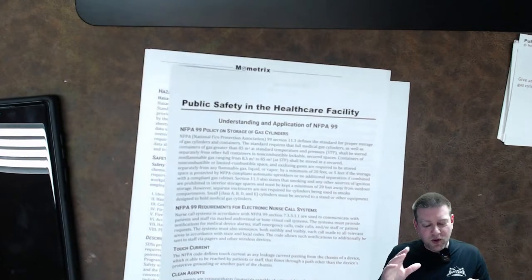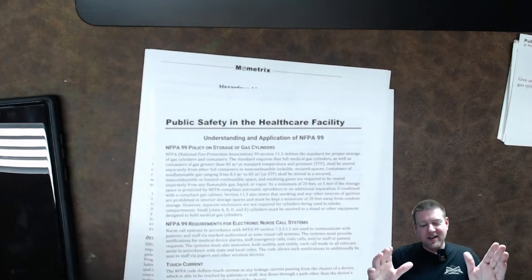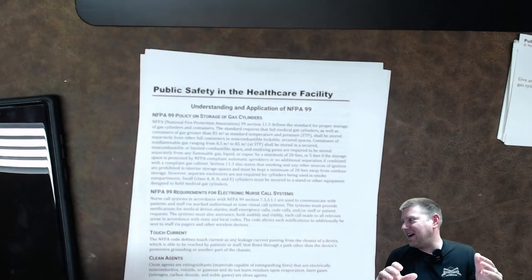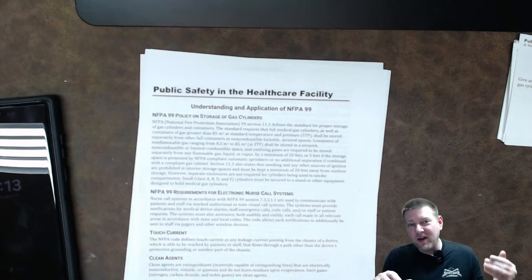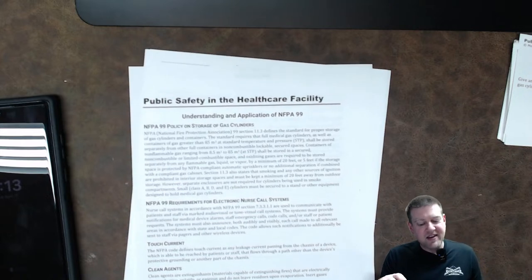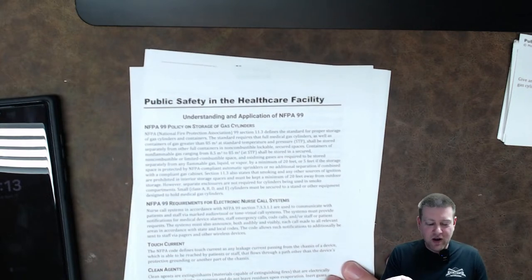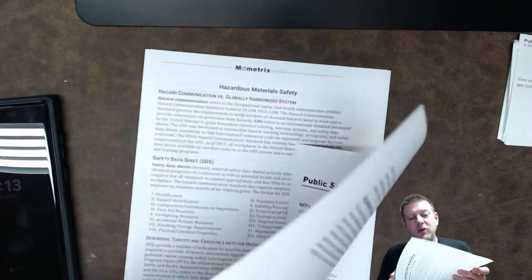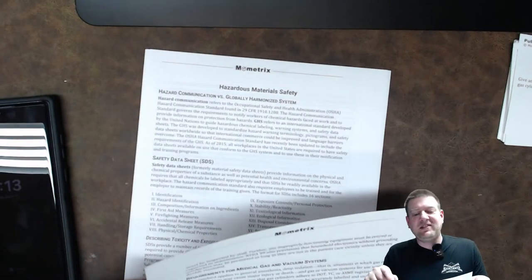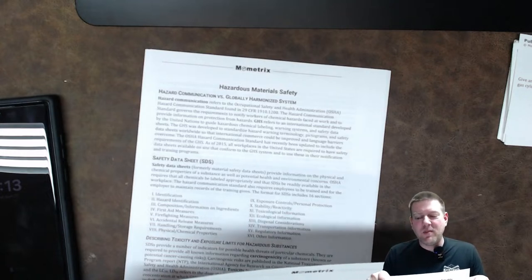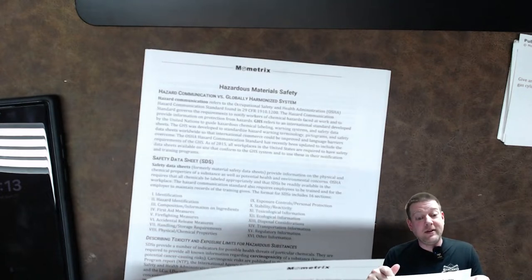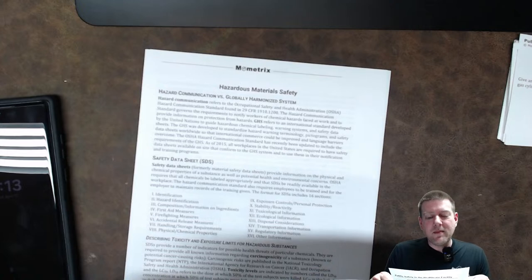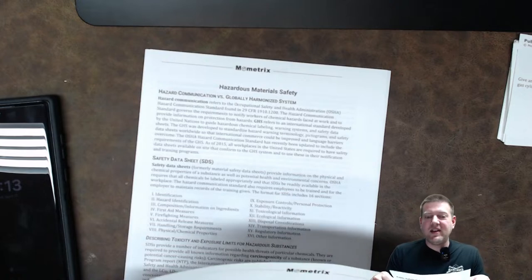Plug-connected, portable, non-medical electronics. Okay, guys, this is one where every hospital has a different policy. I get that. I understand that. However, let's see what NFPA 99 says about it. NFPA 99 requirements regarding AC-powered equipment not related to patient care, which include both facility and patient-owned electronics that the patient will touch during normal use, must be inspected by staff. Further, any improperly functioning equipment must be retired or reported to maintenance.